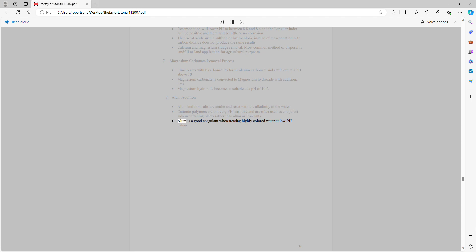Alum addition: Alum and iron salts are acidic and react with the alkalinity in the water. Cationic polymers are not very pH sensitive and are often used as coagulant aids in softening plants rather than alum or iron salts. Alum is a good coagulant when treating highly colored water at low pH values.